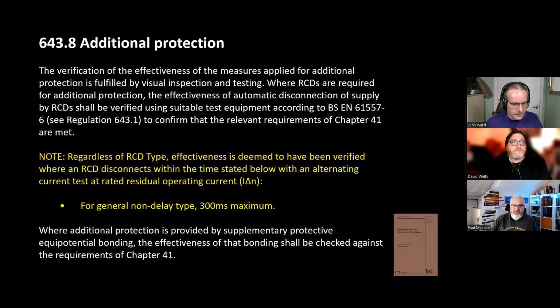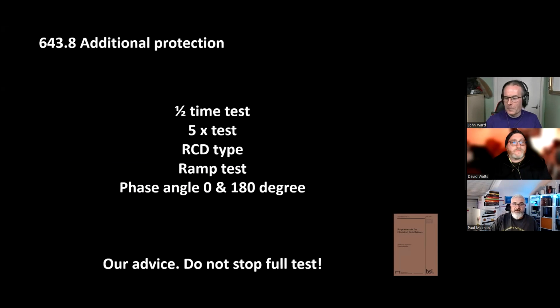So I'm going to happily make a statement here. They did mention that the half-time, 5 times test, the RCD type, the ramp test and the phase angle 0 and 180 degrees, although it's not in the regs, can be used for fault finding and other bits. My advice is do not stop doing the full testing, because I don't want to be stood, or anyone to be stood, in front of a judge where you weren't able to show that you fully interrogated the testing.